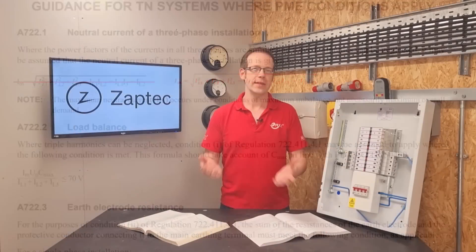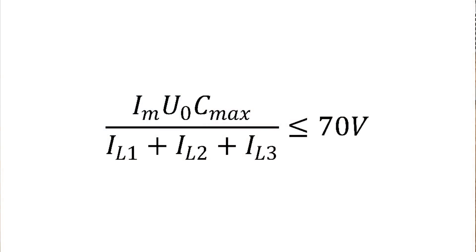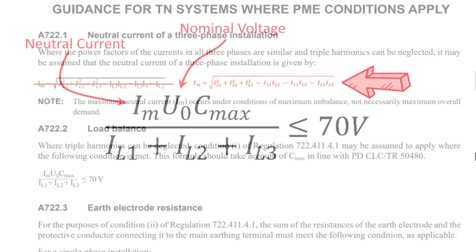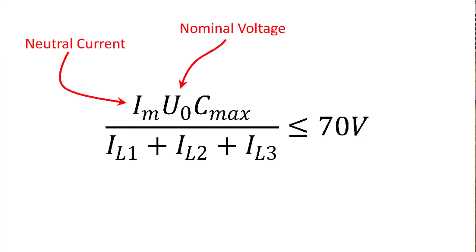IM times UO times Cmax over IL1 plus IL2 plus IL3 is less than or equal to 70 volts. The formula is actually pretty simple—it's just Ohm's law and the power formula all jumbled up together. On the top line, IM is the current in the neutral, which can be found by applying the rather scary formula in A722.1 and is rather dear to my heart as someone who loved teaching electrical science. Then we've got UO, which is the nominal voltage to earth in the system, so 230 volts, and Cmax is just a way of adjusting the voltage to allow for variations to the supply voltage.